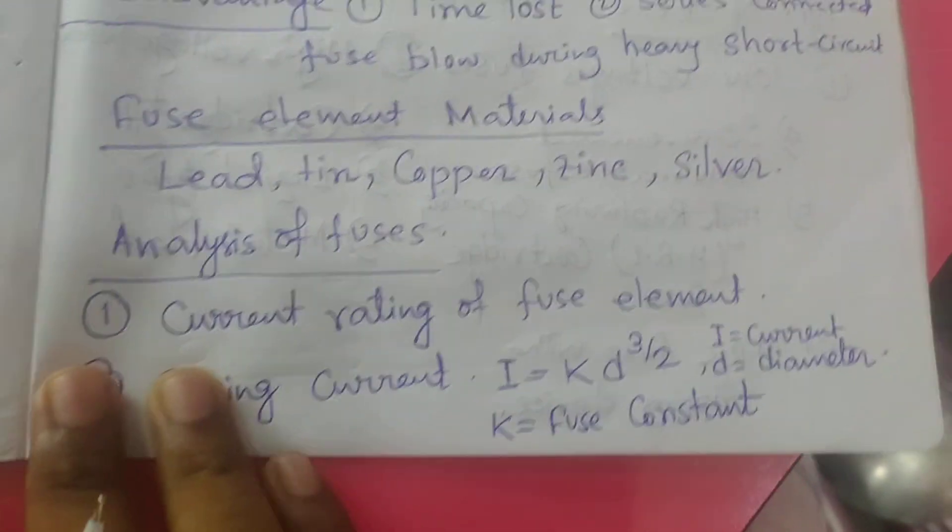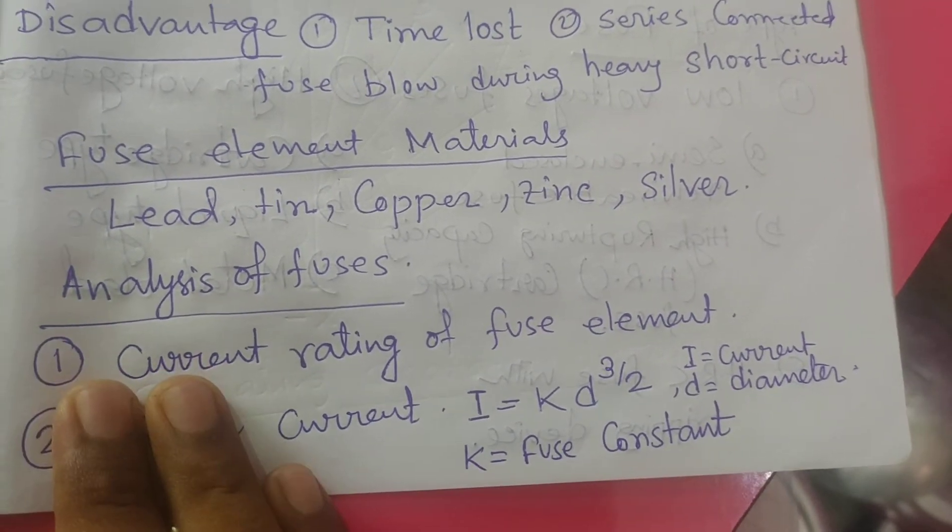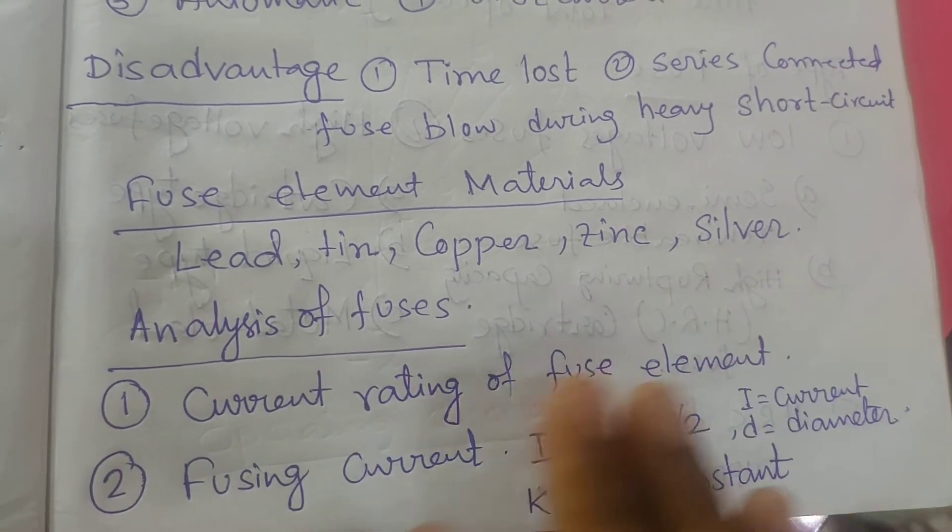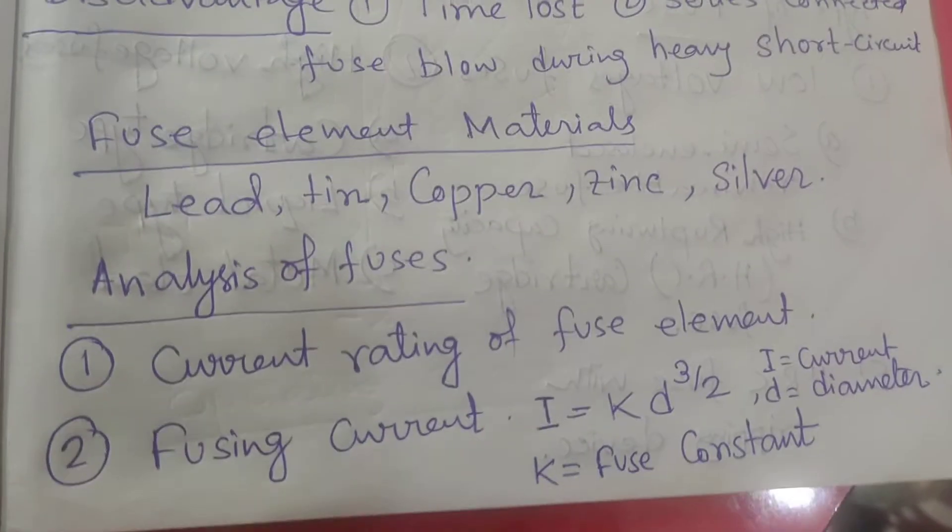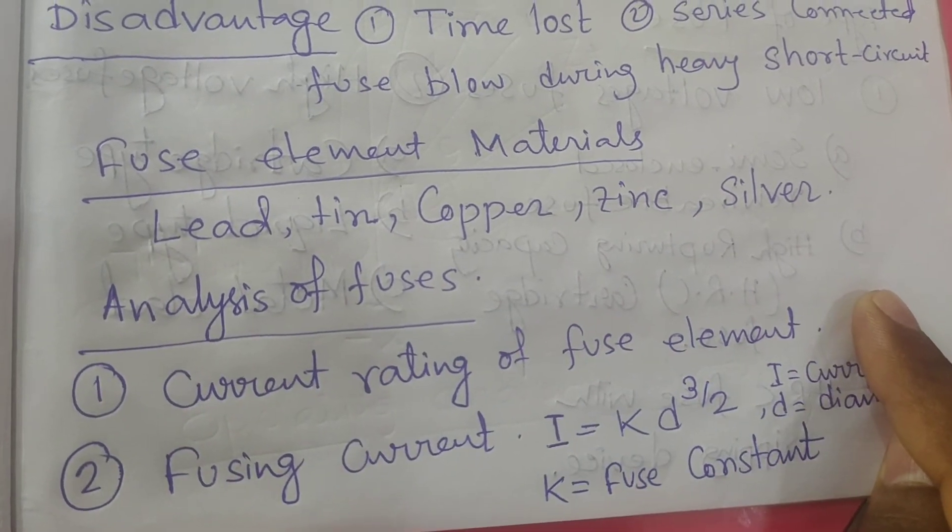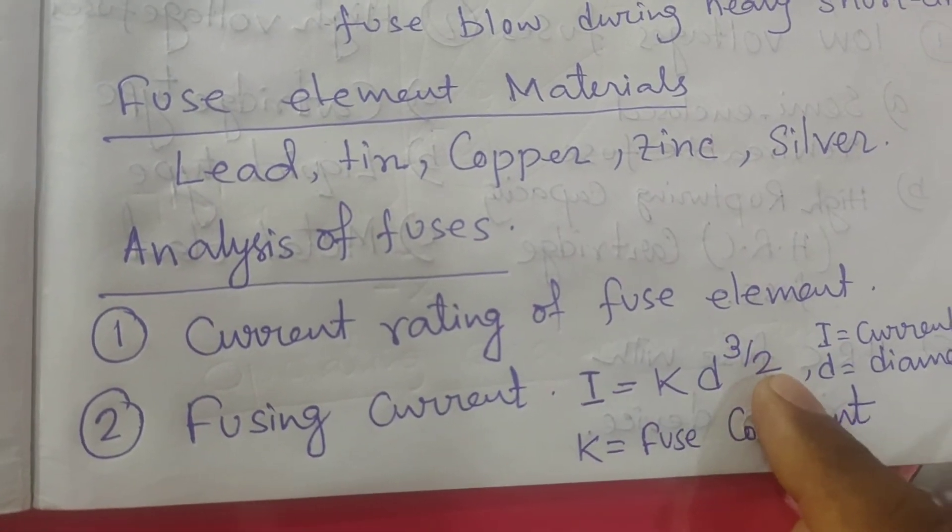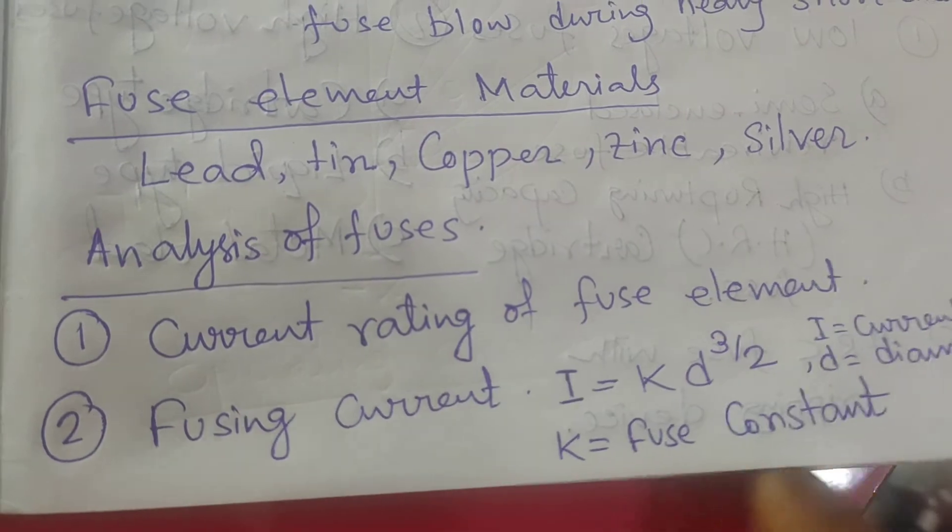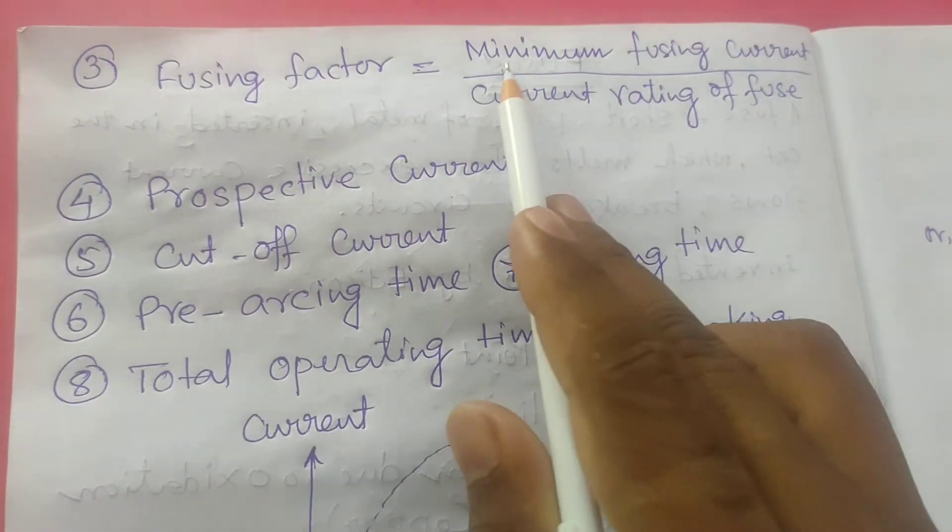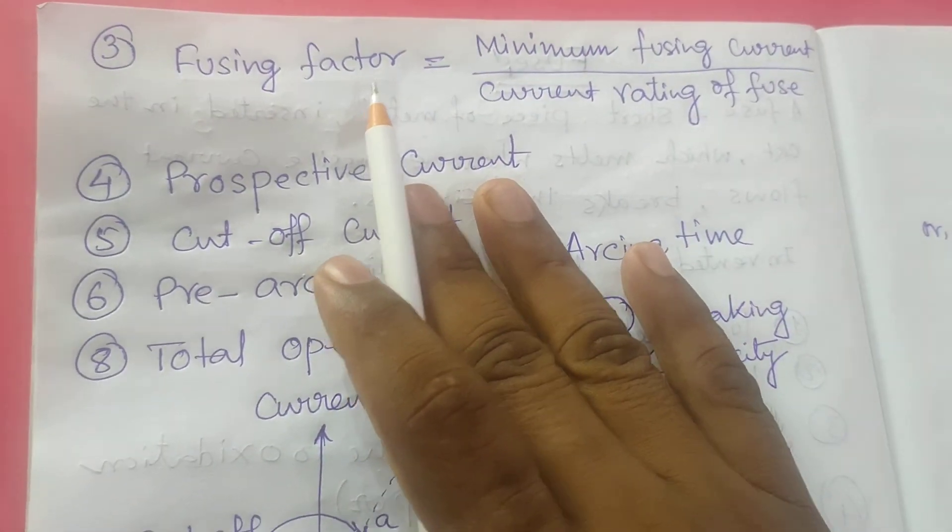Now let's analyze the fuse and what factors and terms are important. First is the current rating of the fuse - what amount of current and load has been connected with your house, industry, factories, or shops. Accordingly, you have to choose your fuse materials. The fusing current: i equal to k d to the power 3 by 2, where i is the current, d is the diameter, and k is the fuse constant. Fusing factor is minimum fusing current divided by the current rating of the fuse.